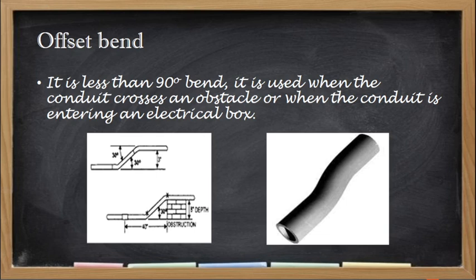The offset bend is less than 90 degrees. Whatever type of bend which is less than 90 degrees is called an offset bend. It is used when the conduit crosses an obstacle or when the conduit is entering an electrical box. A very common use of an offset bend is connecting our conduit into a junction box, utility box, or pull box.